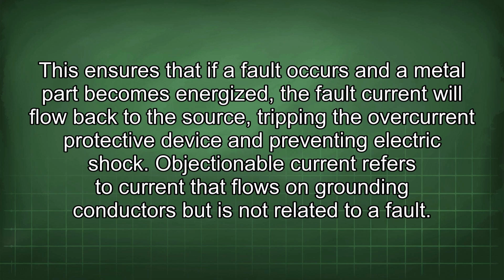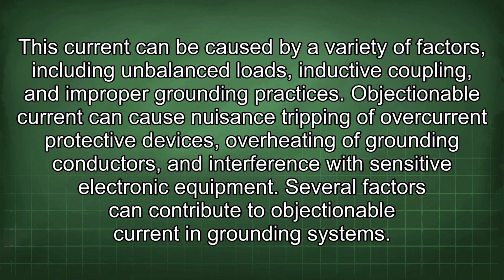Objectionable current refers to current that flows on grounding conductors but is not related to a fault. This current can be caused by a variety of factors, including unbalanced loads, inductive coupling, and improper grounding practices. Objectionable current can cause nuisance tripping of overcurrent protective devices, overheating of grounding conductors, and interference with sensitive electronic equipment. Several factors can contribute to objectionable current in grounding systems.